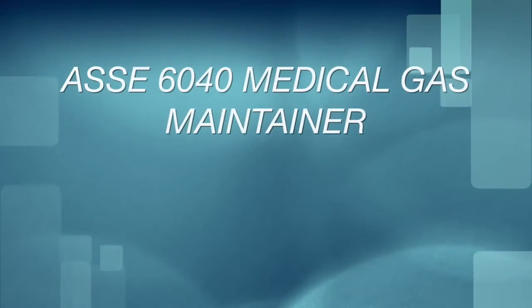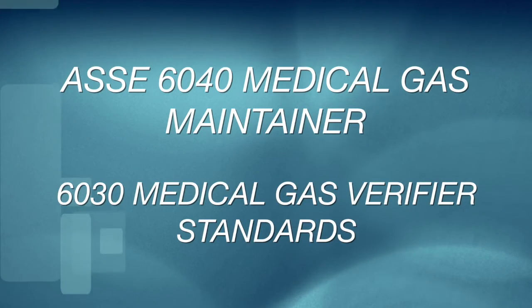Third-party companies that provide services to facilities to test and maintain medical gas systems are now required to hold credentials in accordance with the ASSE 6040 Medical Gas Maintainer or 6030 Medical Gas Verifier Standards.